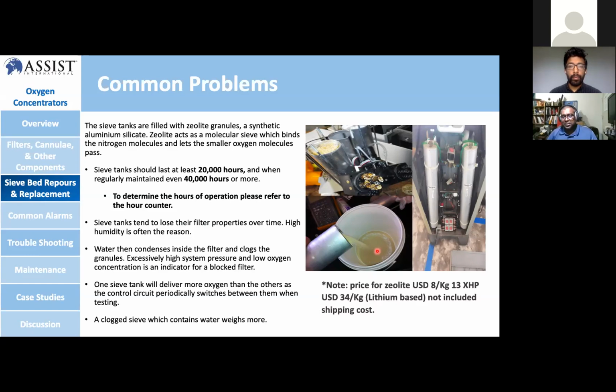So the sieve tank tends to lose its filter property in the long run, if more than 20,000 or 40,000 hours. But at the same time, if the place is very humid, the lifespan will actually reduce. Because what happens is, when the air intake goes in, the humidity is very high, it ends up in the sieve tank. When you pressure up, you send it to the sieve tank. Eventually, the lifespan reduces because of that.